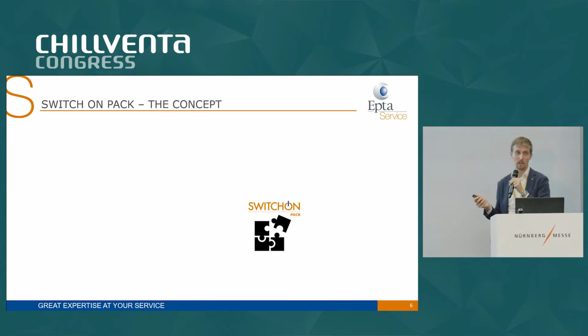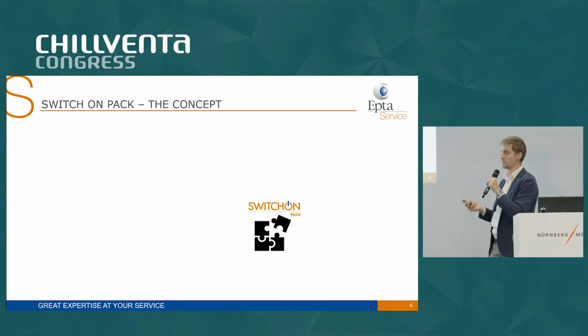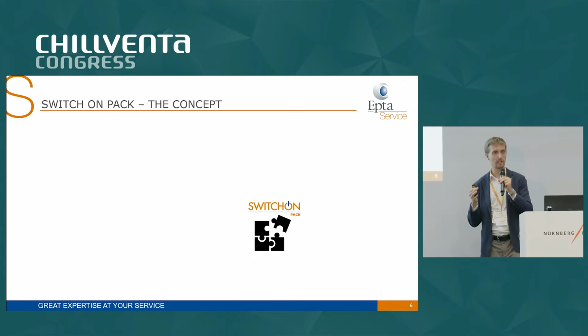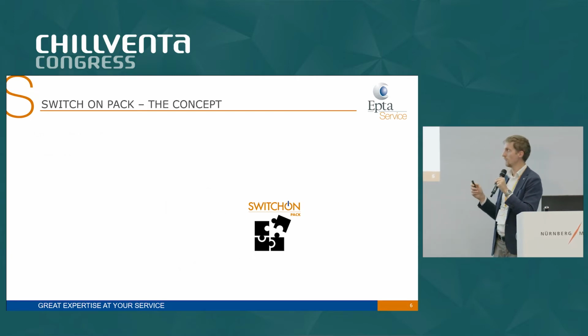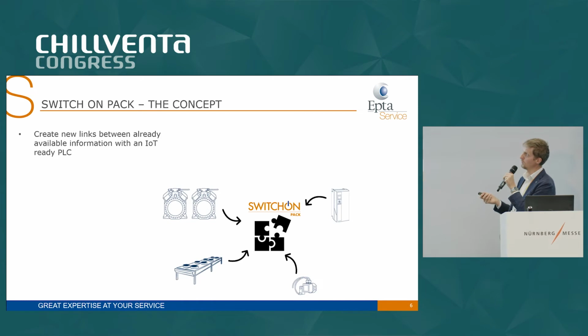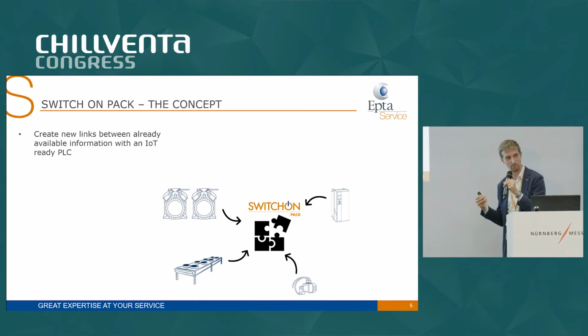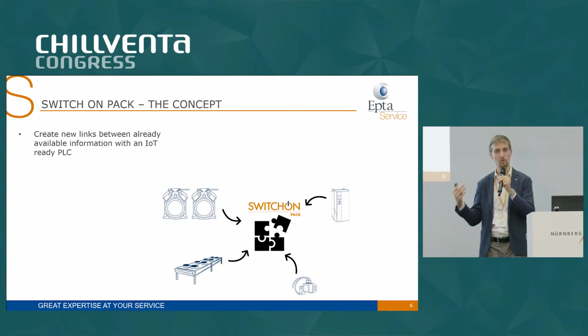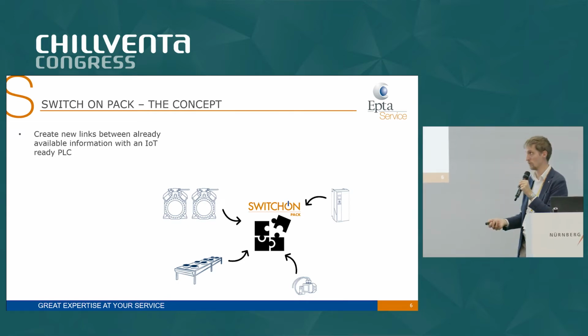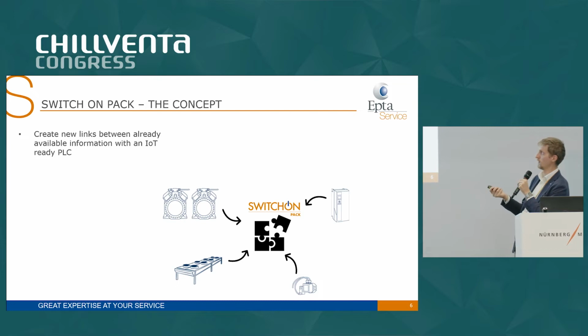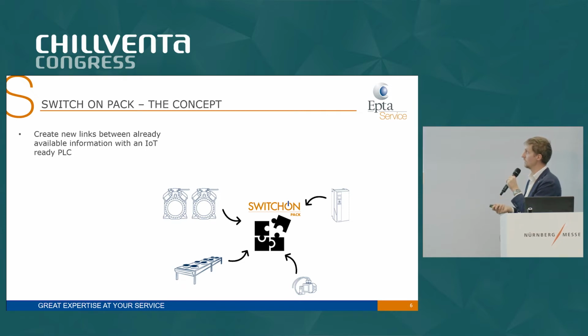Starting from this background, we conceived the Switch on Pack platform. Its core is made of an IoT-ready PLC that creates links between devices that are already able to generate data and communicate it through communication protocols: the driver of the pack controller, the gas cooler fans, oil injection, and inverters.